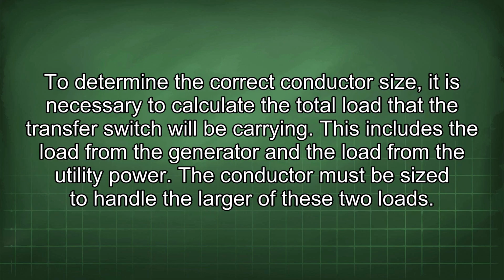To determine the correct conductor size, it is necessary to calculate the total load that the transfer switch will be carrying. This includes the load from the generator and the load from the utility power. The conductor must be sized to handle the larger of these two loads.